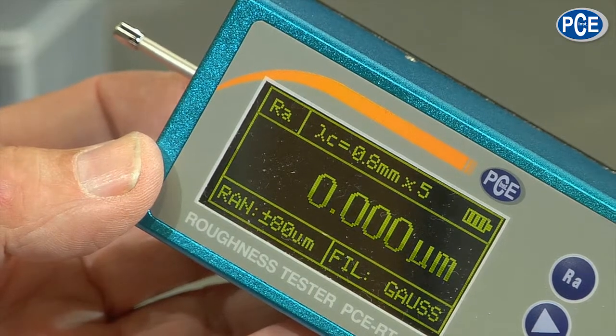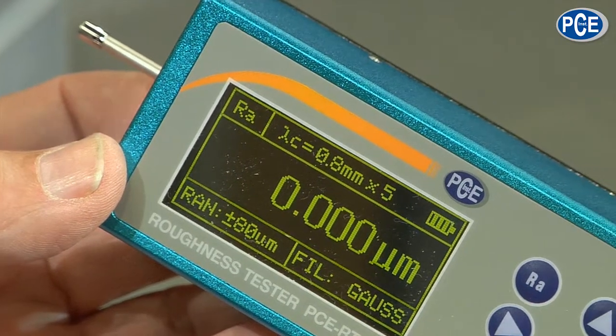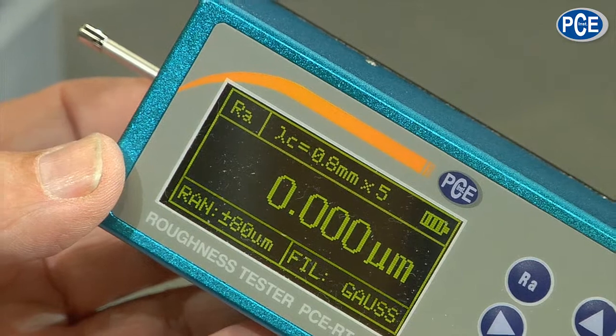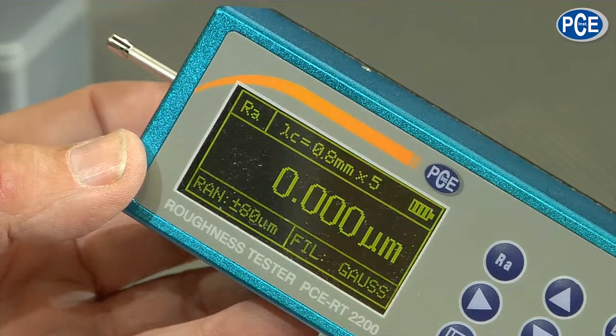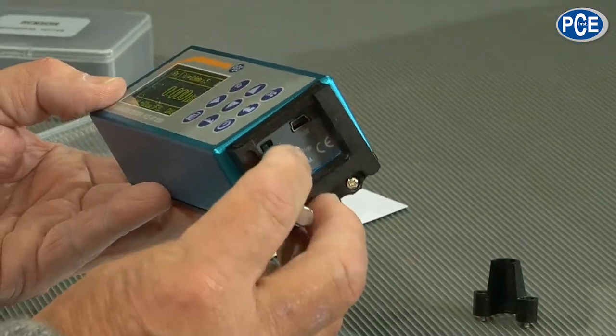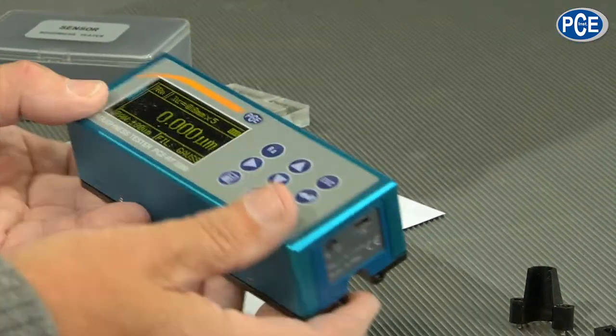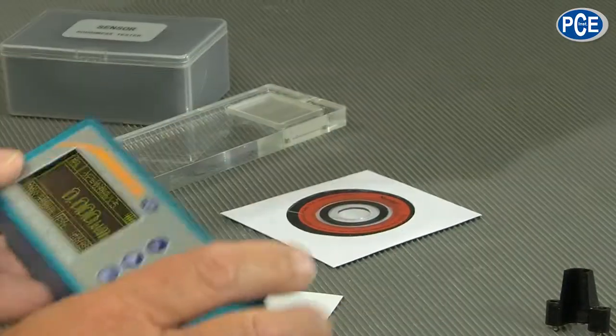Now we have something else. The touch head has to have a certain distance to the probe, and when the touch head is bent or the probe has a different height, I have to set it right. For this we have on the side a foot to screw onto, and with this I have the possibility to compensate different heights. That means I can change the angle too.